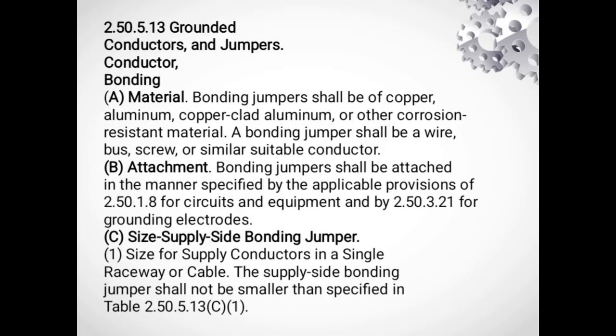C. Size, supply side bonding jumper. 1. Size for supply conductor in a single raceway or cable. The supply side bonding jumper shall not be smaller than specified in Table 2.50.5.13 C1. Section 2.50.5.13 outlines requirements for grounded conductors, bonding conductors, and jumpers. This component must be corrosion resistant and properly attached. The size of the supply side bonding jumper is determined by the size of the supply conductors.